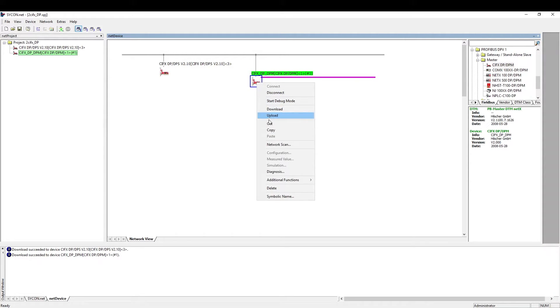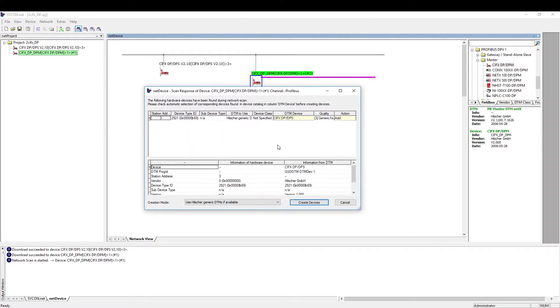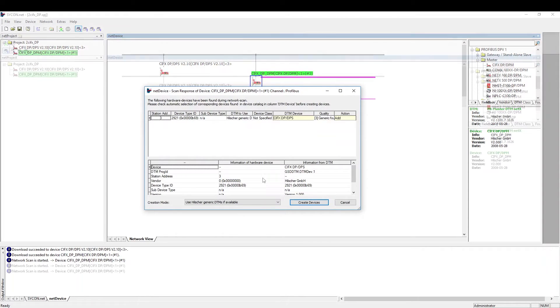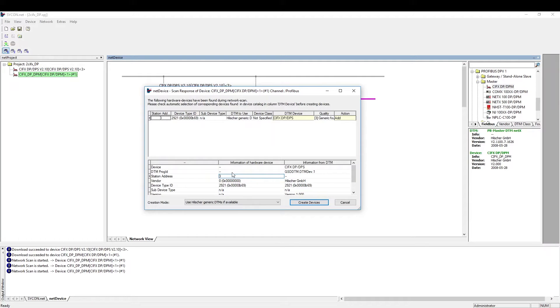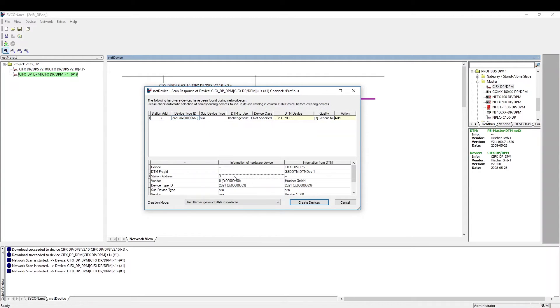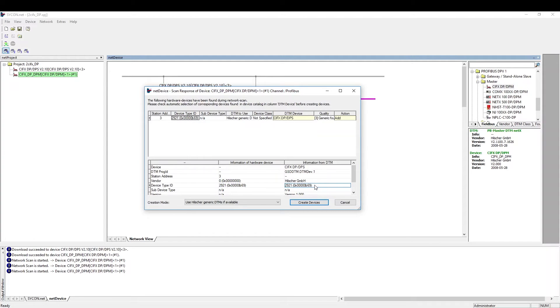We now choose network scan. The network scan has properly detected the CIFX card. We can see the correct station address and device type ID. If there are several GSD files for the same device, the column DTM device will be yellow, indicating we have to choose the correct version of the GSD file.